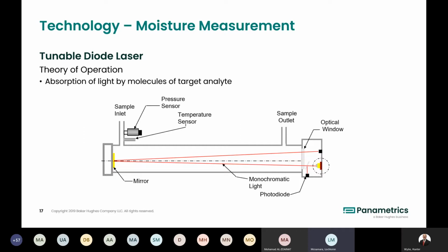The light passes through the measurement chamber, hits a mirror and is reflected back through the optical window into the measurement head. We have some photodiodes there. Initially, we measure the full intensity of the light because it's unattenuated. That's a very dry environment. There's desiccant in there, so it's less than 1 ppm of moisture. Then the signal photodiode measures the attenuated signal, and fundamentally we're measuring the difference between the unattenuated signal and the attenuated signal, and we're able to derive the moisture content from that.